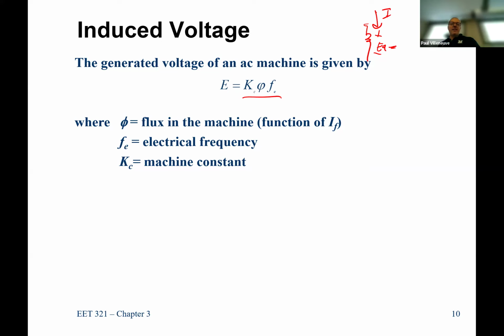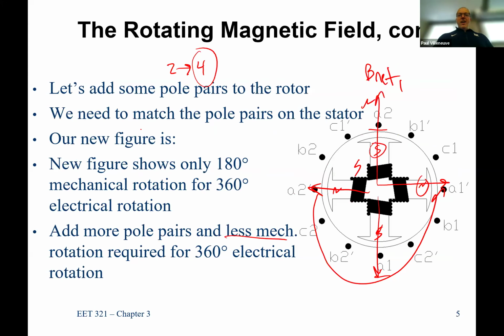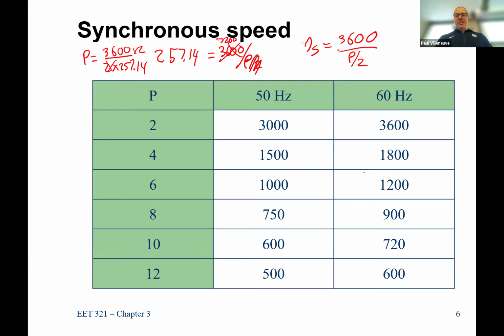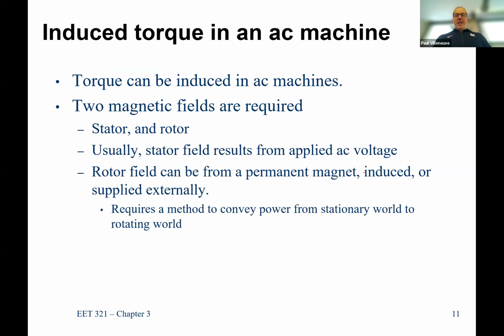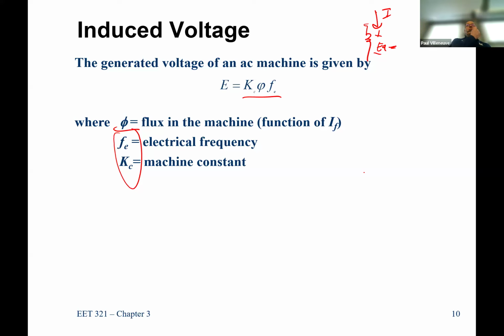You have a machine constant K, you have a flux, and you have an electrical frequency there. These two can't be changed. 60 hertz, and a machine constant is a machine constant. The only thing that you can change is the flux in the machine. So you can either increase or decrease the amount of flux. One way to do that, as we talked about over here, is that you can put more or less DC energy into these windings. Another thing you can do is, if you're trying to pull more power out of the machine, you're running more current into the machine, and that makes it have a higher value of flux. So you can balance the machine just by putting more load on it.